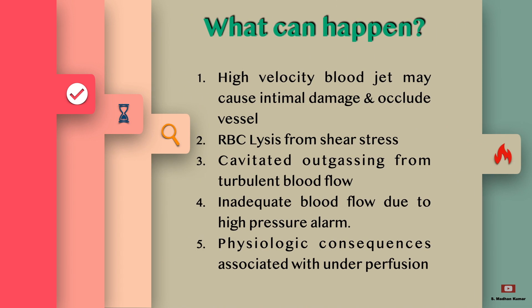What happens when we use an undersized aortic cannula? High velocity blood jet can cause intimal damage and occlude the vessels, RBC lysis due to shear stress, cavitated outgassing from turbulent blood flow, and inadequate blood flow due to high pressure alarm, along with physiologic consequences associated with under-perfusion.